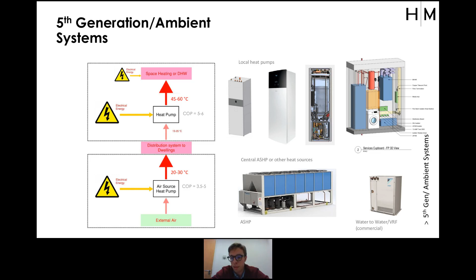So I was going to go on to a case study of that. On Manor Road in Canning Town, it's currently on site at the moment, and it's looking at this 5th generation network and some of the key benefits, and the reasons why we looked at the 5th generation. With the 4th generation, we didn't have enough plant space on the roofs for an instantaneous load, and I'll come on to diversity in a short while. So that was a key consideration. Also, incoming electrical supply: we estimate potentially a six-figure saving in terms of incoming power with this system, because the operation is low in terms of instantaneous peak load on the central plant, and the saving was significant. We didn't have to have extra substations and so on.